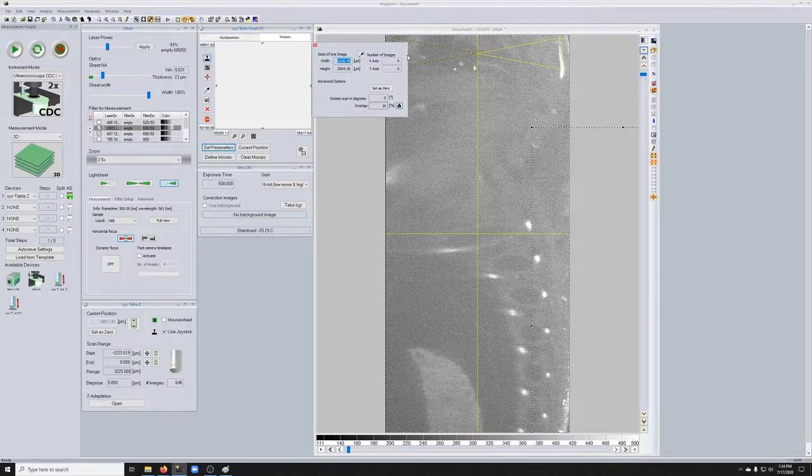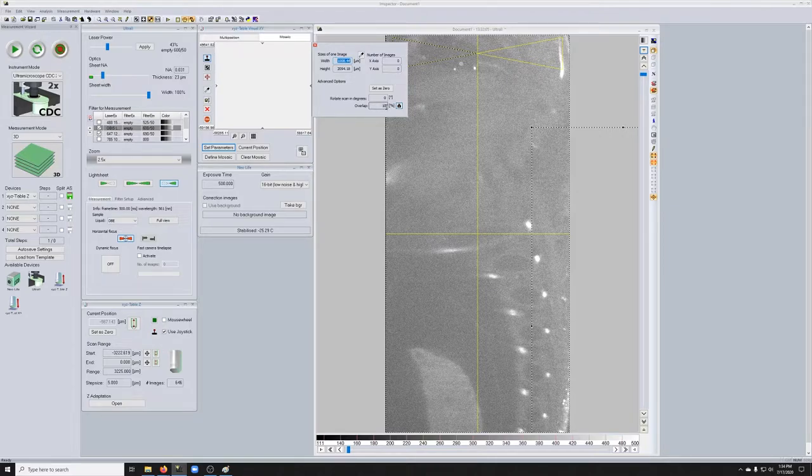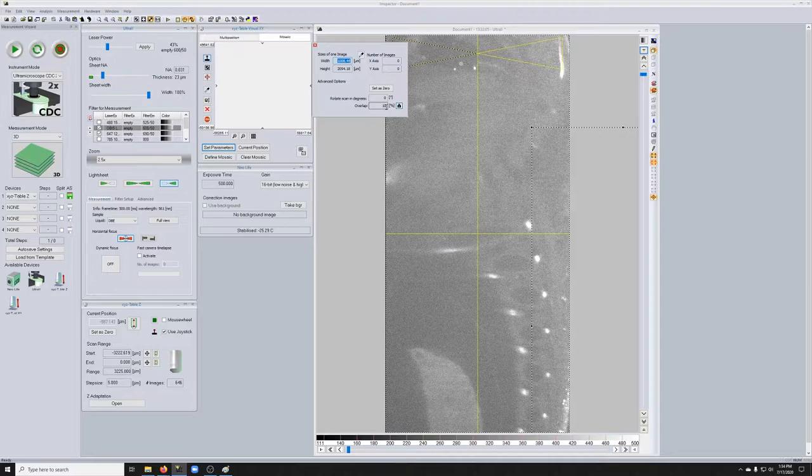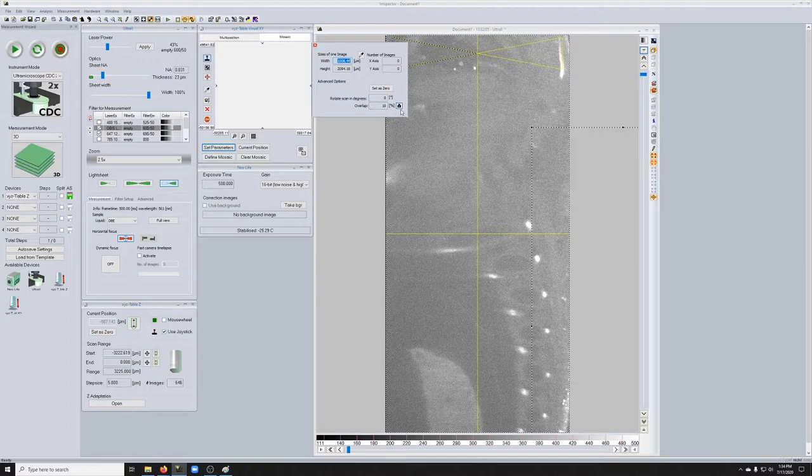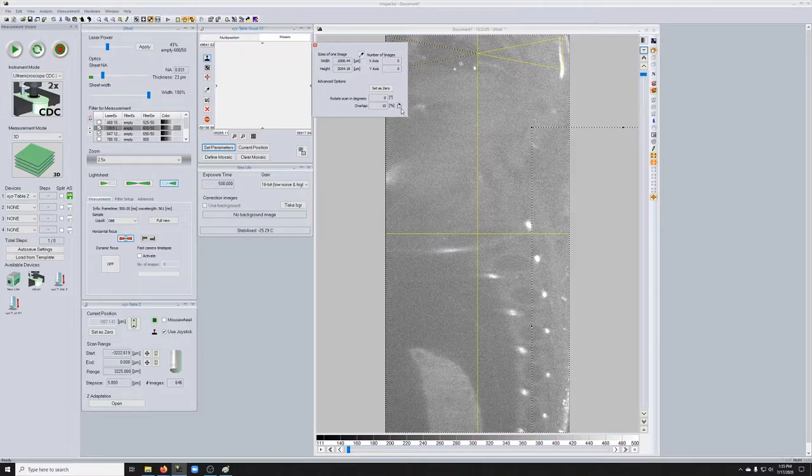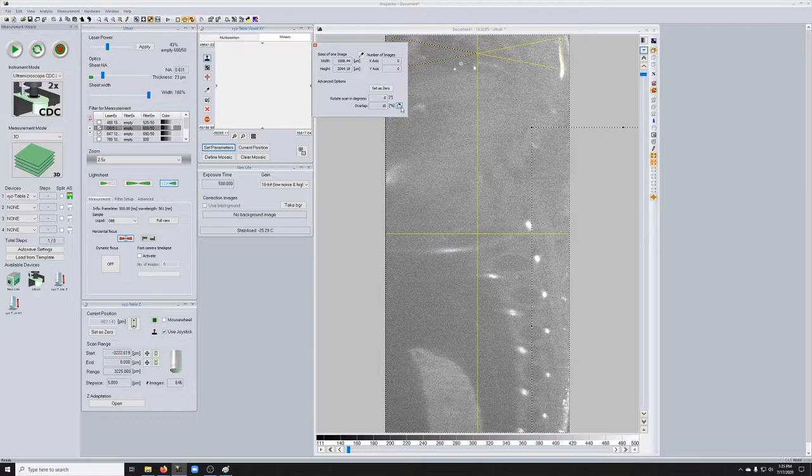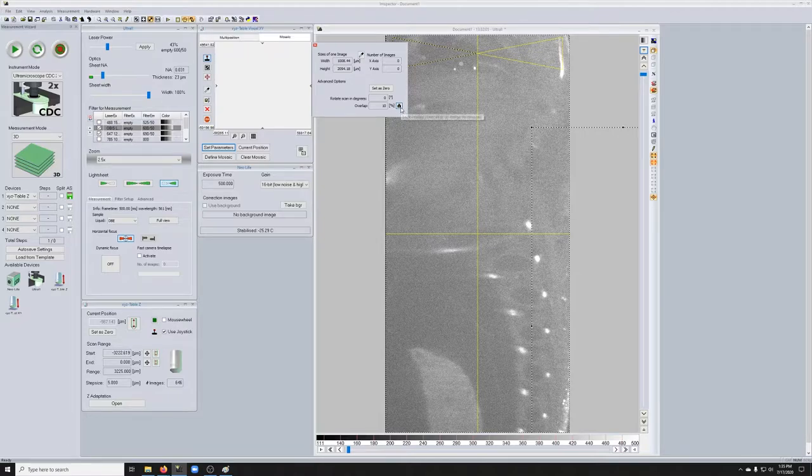Verify that the lock button is closed. So this button should be in that position, you shouldn't need to change it. But if it looks like this, make sure you bring it back to the locked position. Because when you're cropping, this is what ensures that this overlap is respected properly. If you're cropping and you have it like this, it's not going to move the stage to the right position. So it's the default, but since it's a setting that you could conceivably touch, make sure it's in the black locked with the little plus sign condition.